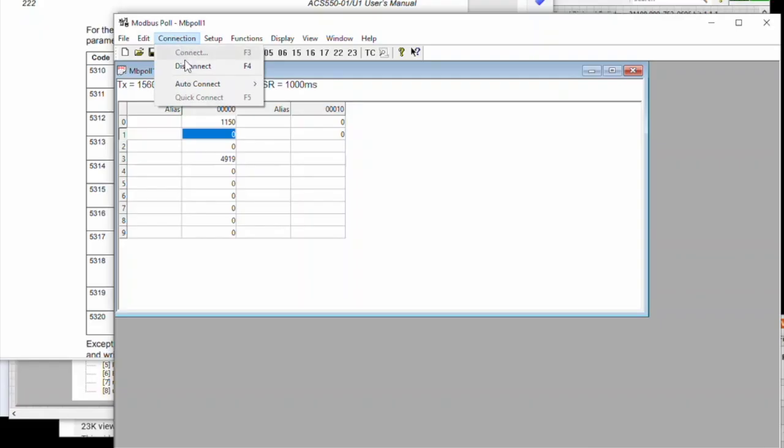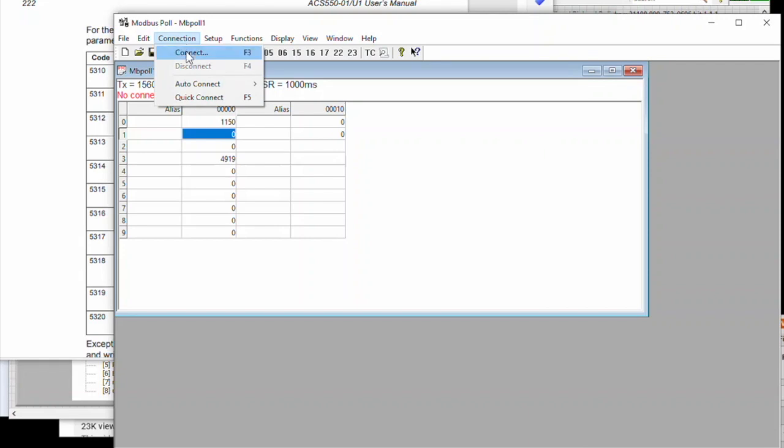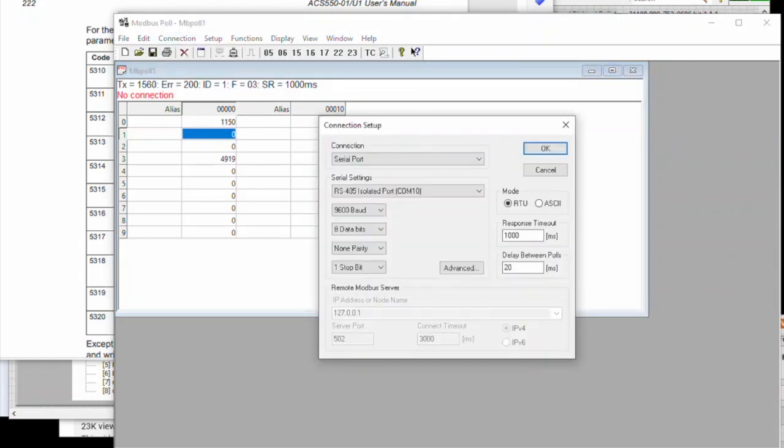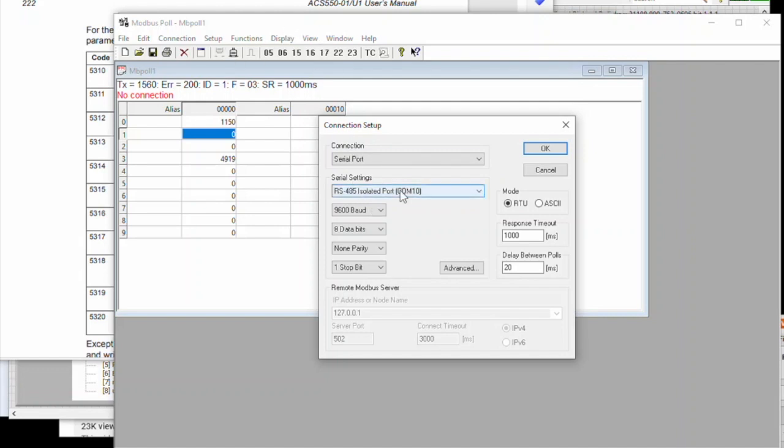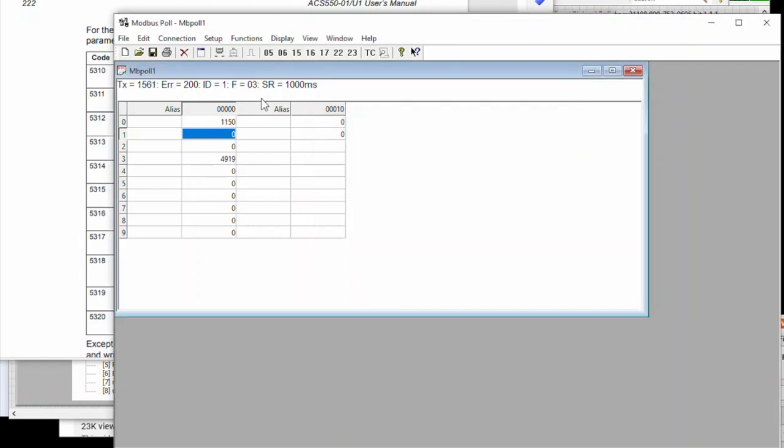Here's how to communicate to the ABB ACS 500, 510, 550. Connect to the thing using Modbus Poll. It's 9600, 8, none, 1, and RTU. Nothing else is checked. One second delay.